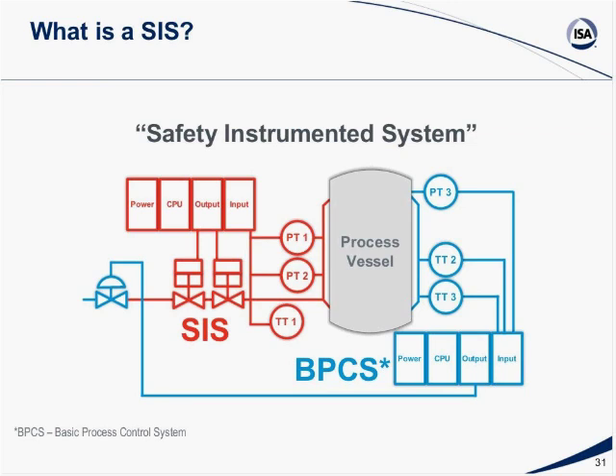Now, let's talk a bit about what is a SIS. There was a question previously asked where they saw a safety system and a BPCS side by side to one another. This is exactly the same diagram, where you see a process vessel with temperature transmitters and pressure transmitters in blue, with power and CPU and inputs and outputs all in blue. But then you also have a safety system on the left, even though it looks like a parallel system. What the safety system is doing is that it has a separate PLC or a separate independent system, which is also monitoring some of the pressure and temperature parameters.